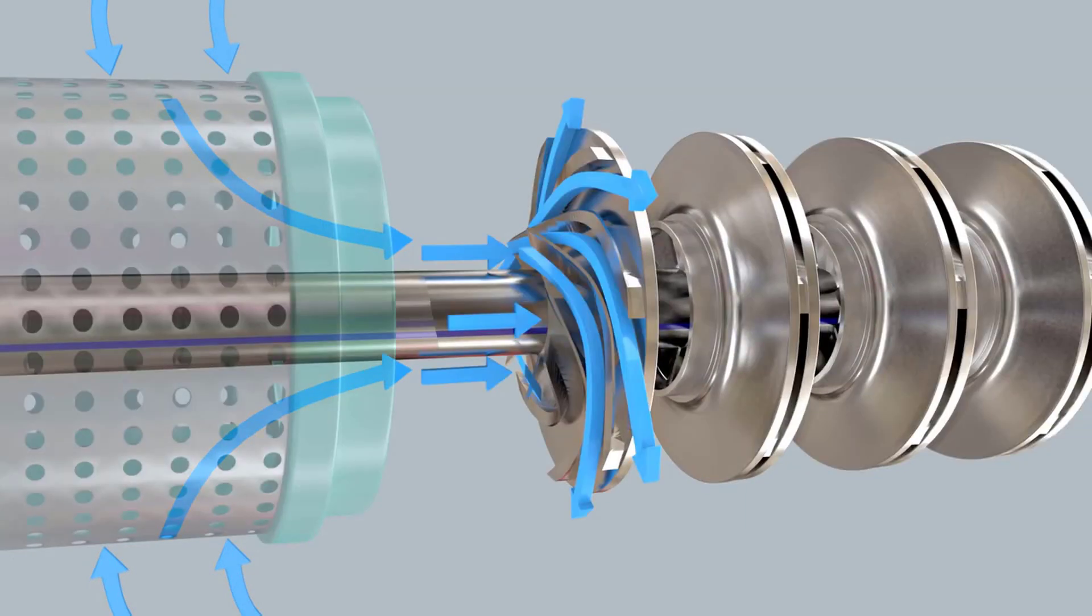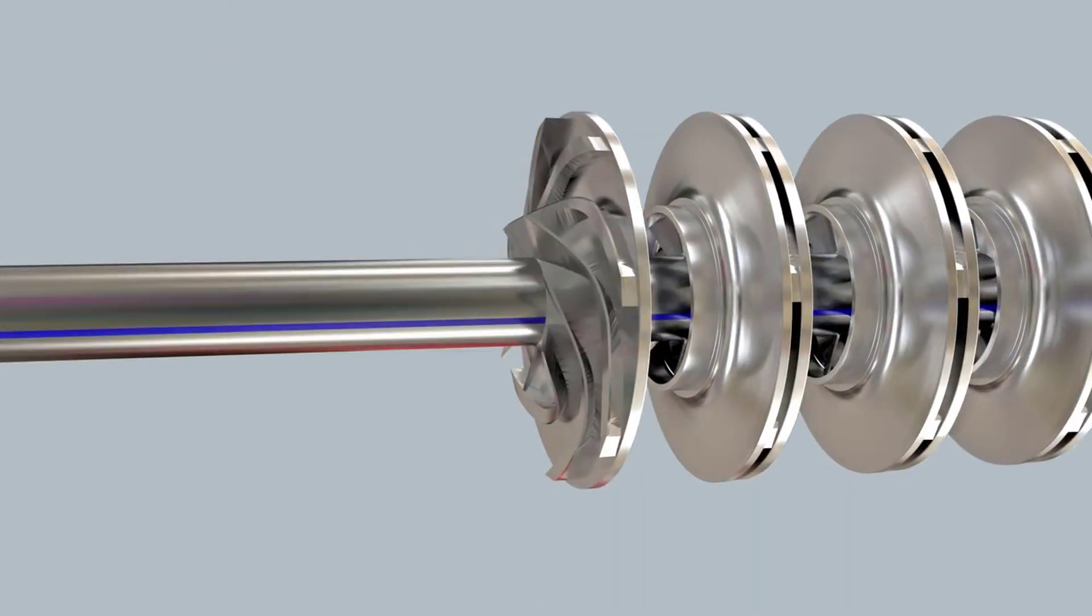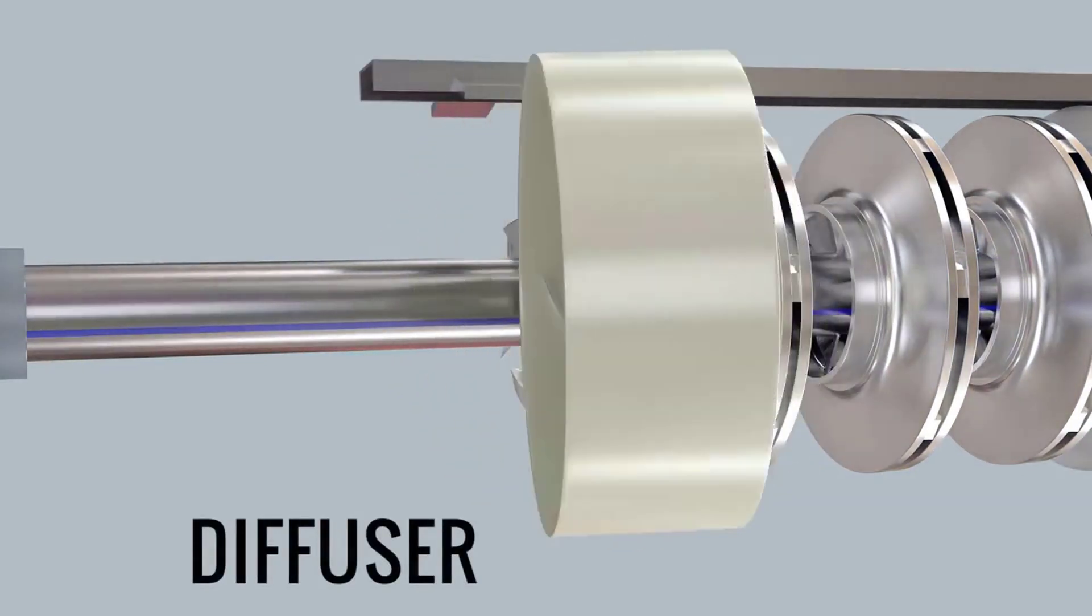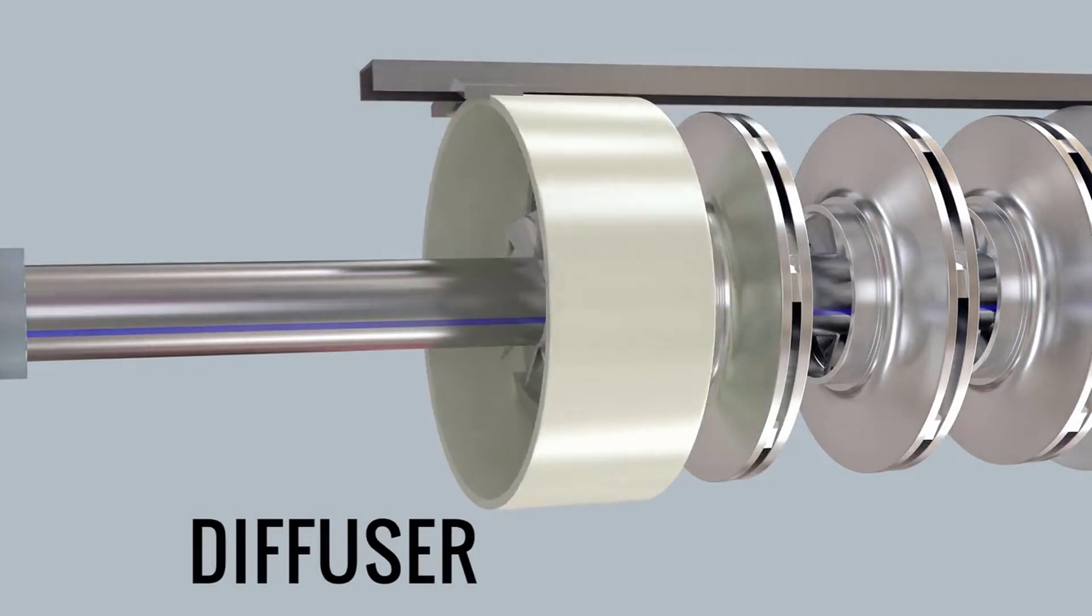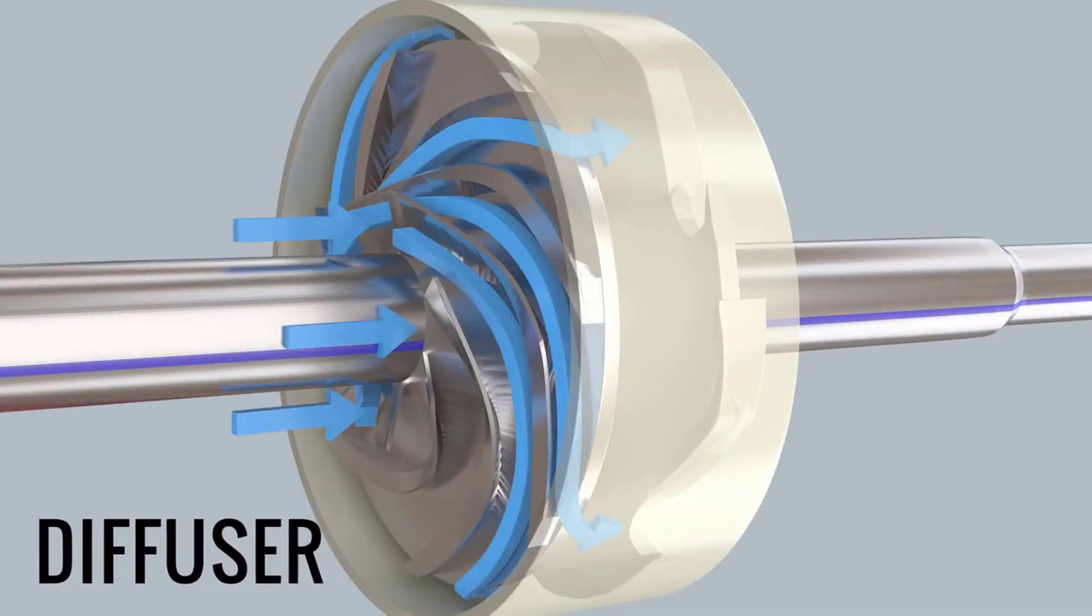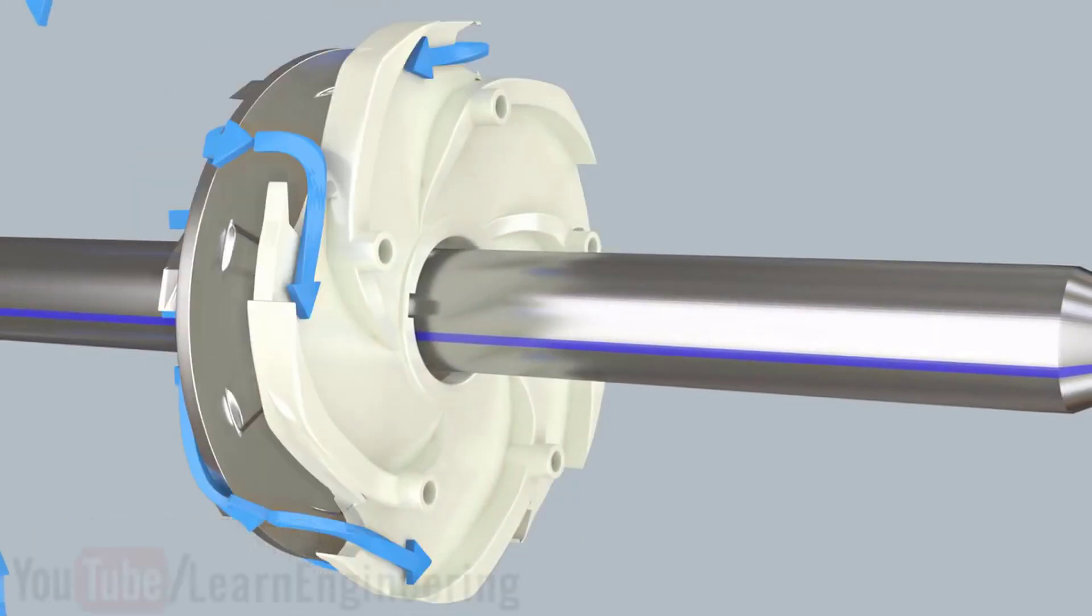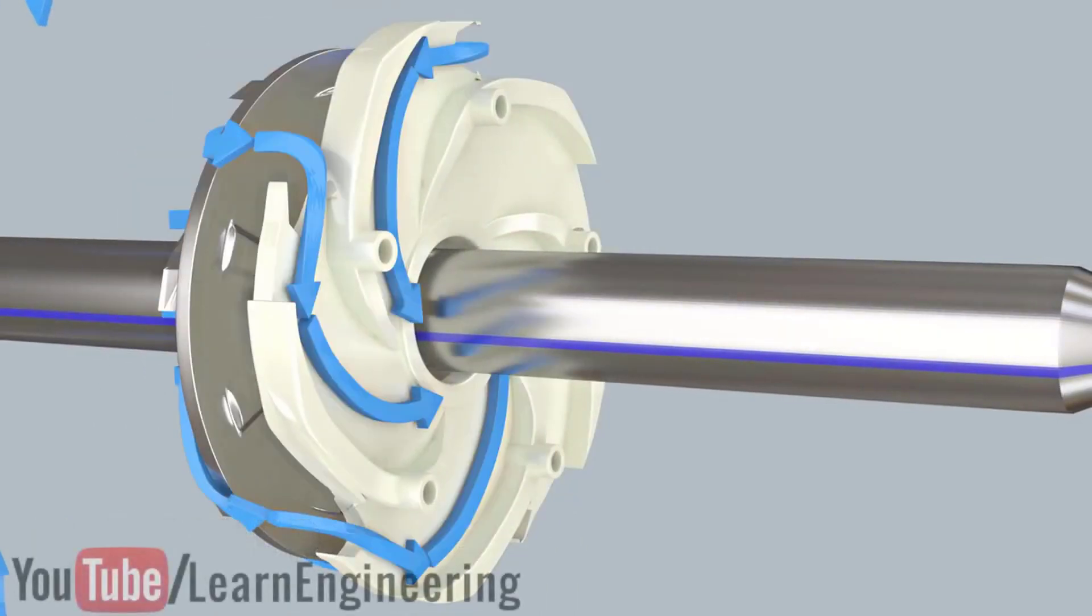The water enters through the eyes of the impellers, and they are then thrown out radially due to centrifugal action. This way, the water particles gain both kinetic and pressure energy. Now we need to pass this outlet water to the next impeller efficiently. A stationary device, called a diffuser, is used for this purpose. You can see how the water flowing from the impeller enters the diffuser. The diffuser then deflects the inlet water and makes it ready for the next impeller stage.